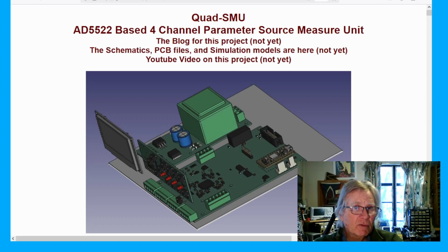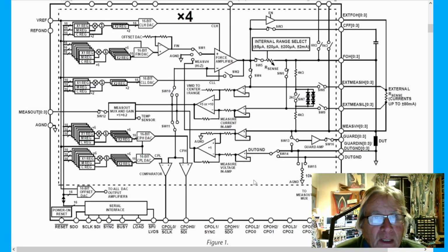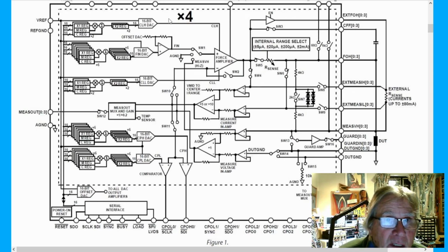AD5522 is a pretty powerful chip. Let's get into the block diagram for the AD5522. This is one channel of the source measure unit, and there are 4 of them on the chip. And what we see starts with a force DAC, and that's a 16-bit D to A converter with some scaling. That goes into the force amplifier, and then the force amplifier through the internal range select feeds the force output, which feeds the device under test.